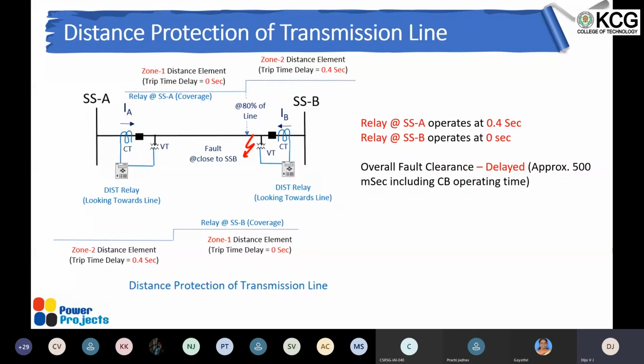But in the case of a fault close to the other end breaker, at the remote end, it goes beyond the 80%, right? So we can expect that the substation B relay operates immediately, but the substation A relay operates at 400 milliseconds. I mean, it goes to the zone 2 timer and operates with a 400 millisecond time delay. This is generally not accepted in the case of 400 kV, or even on some critical 220 kV lines, because if the fault clearing time is delayed in a transmission network, it's going to cause stability issues. Because of that, we have to ensure that it operates instantaneously for a fault anywhere in the system. So with this simple distance protection arrangement, you cannot do that.